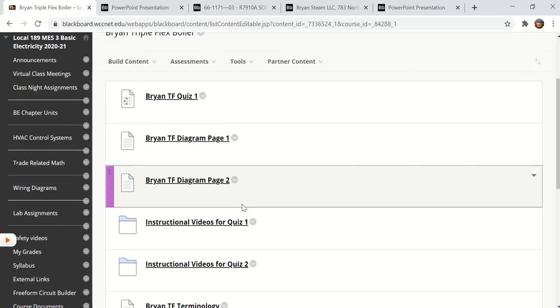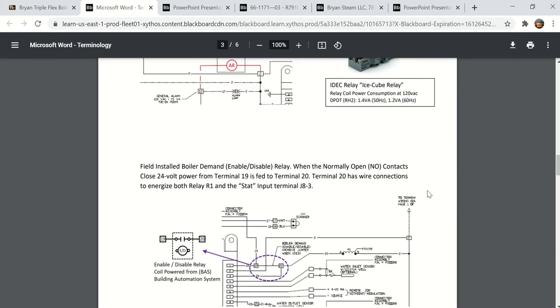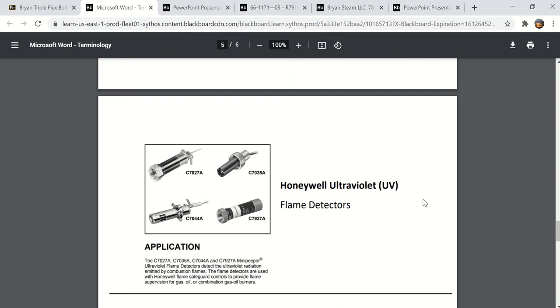So let's go back and look at the terminology page. And as we scroll down here, you'll see this is the pictures of the Honeywell ultraviolet scanner. You've probably seen these on boilers before if you looked close enough. It actually sees ultraviolet radiation. Right here it says that what they call the mini peeper is an ultraviolet flame detector that detects the ultraviolet radiation emitted by combustion flames, and that's how the controller knows that there's actually flame there.